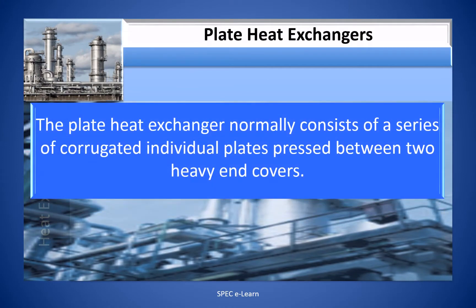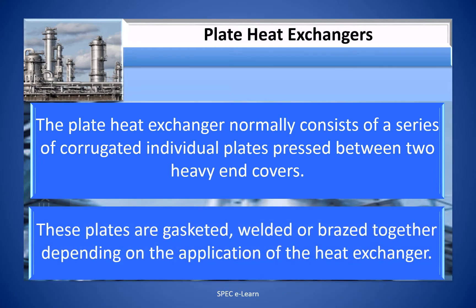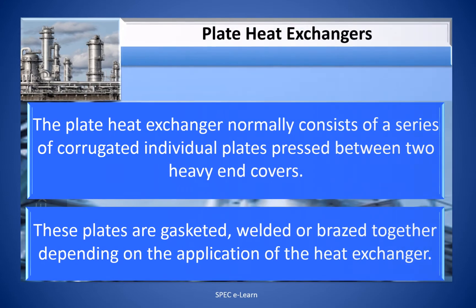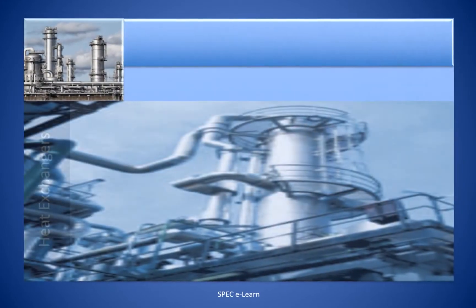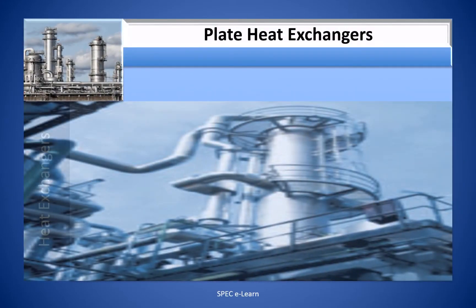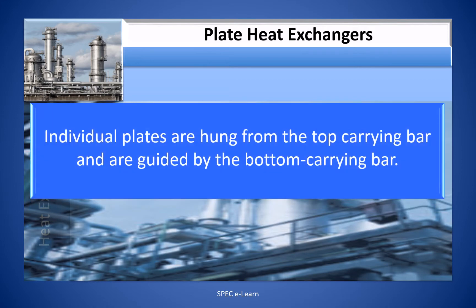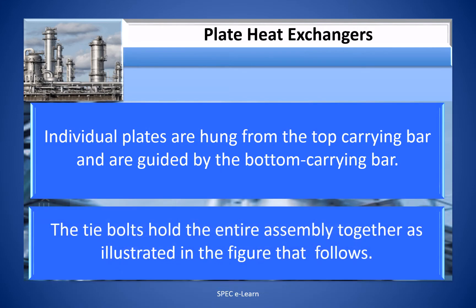The plate heat exchanger normally consists of a series of corrugated individual plates pressed between two heavy end covers. These plates are gasketed, welded, or brazed together depending on the application of the heat exchanger. These plates are hung from the top carrying bar and are guided by the bottom carrying bar. The tie bolts hold the entire assembly together as illustrated in the figure.